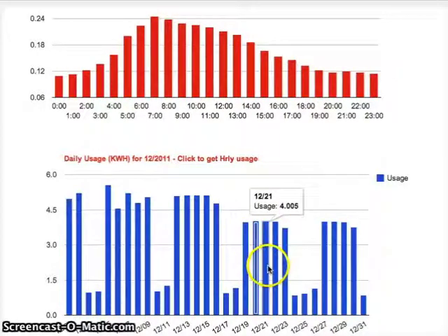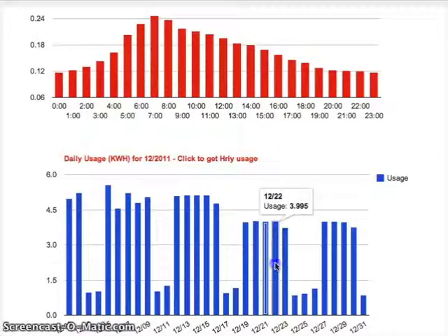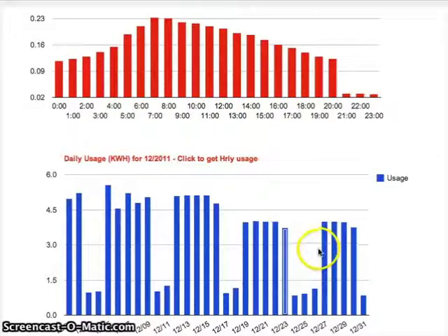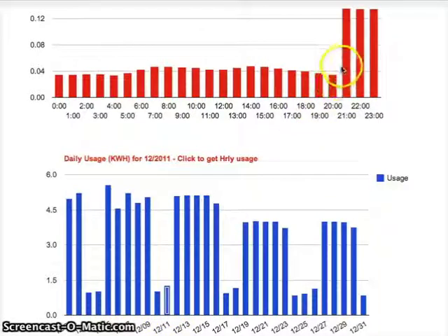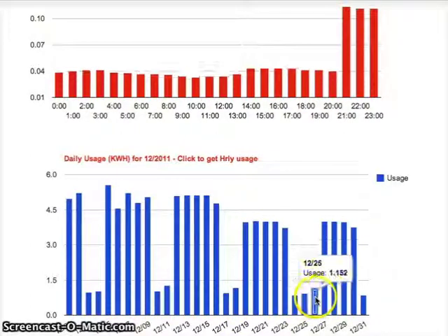As we click through, most of the days follow a similar pattern, so this sample building is pretty well behaved, but there are some unusual things we might want to take note of. For example, there is a sharp increase on Sunday evenings at around 10 p.m. when some of the weekday process loads seem to come on, so you might want to find out if this is the intended start time.